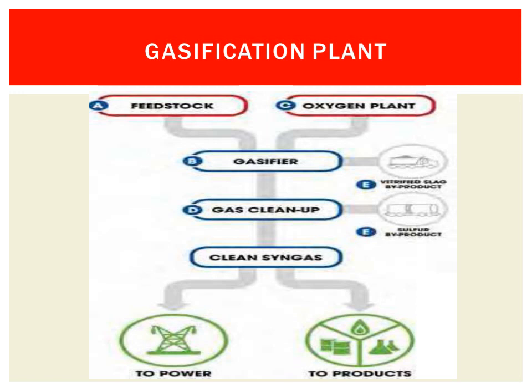Most solid and liquid feed gasifiers produce a glass-like byproduct termed slag, which is non-hazardous and can be used in roadside construction and as a roofing material. In most gasification plants, more than 99% of the sulfur is removed and recovered either as elemental sulfur or sulfuric acid. After cleaning, the syngas can be recovered and used for various purposes like electricity generation or for forming chemicals in industries. This is the overall gasification process where feedstock and oxygen are injected into the gasifier, syngas is released, cleaned up, and used for various purposes.